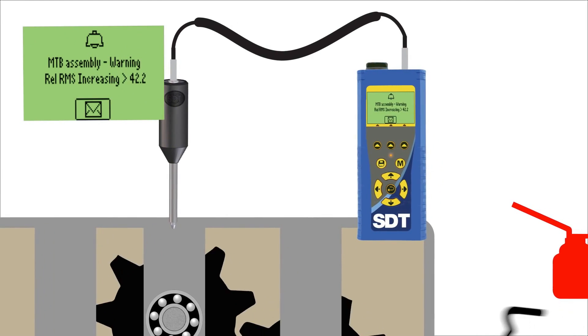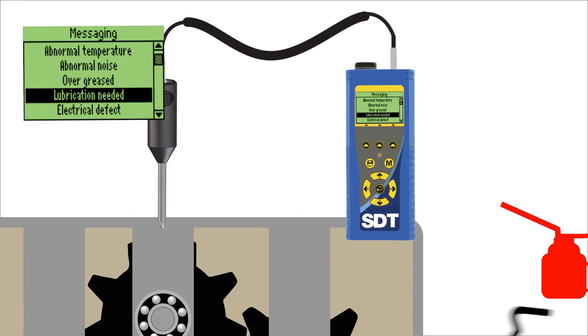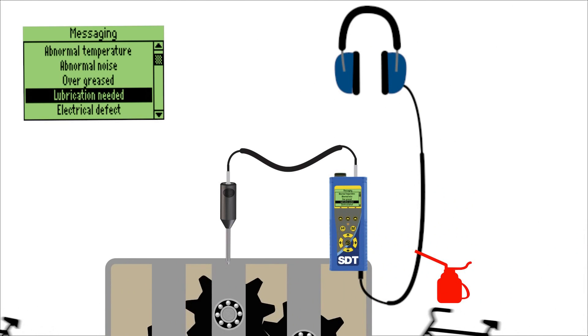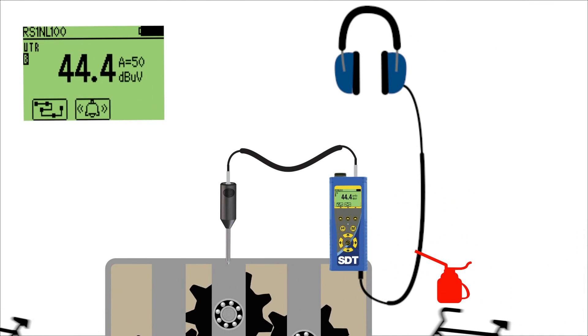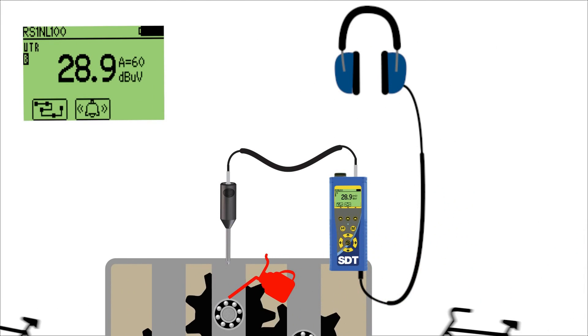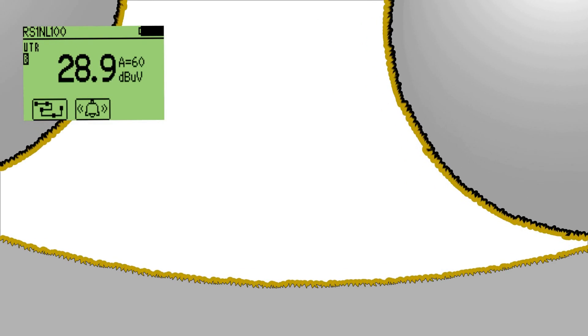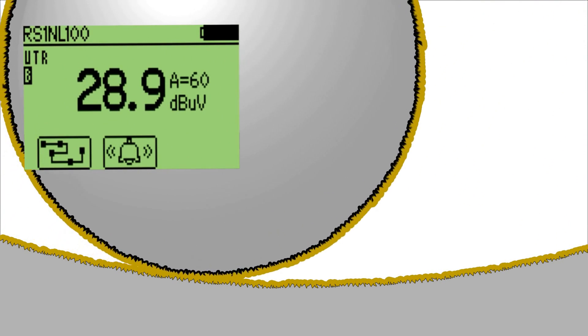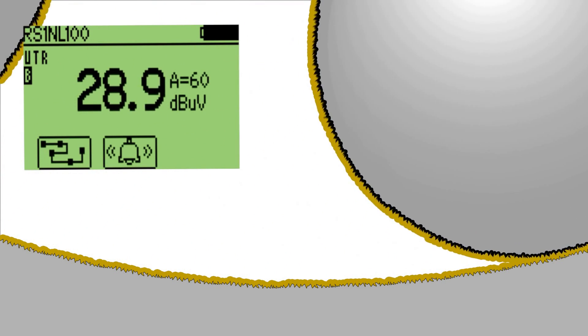In addition to alarming when friction levels need attention, lube techs listen to the bearing as new grease is applied. Using the SDT270's digital decibel metering as a guide, only enough grease is applied to return the bearing's friction level to normal.